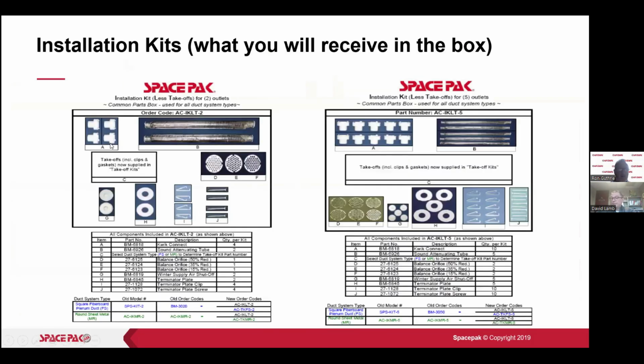Okay, these are the kits. They come with sound attenuators and connectors for the tubing. You've got your outlets, winter shutoffs for cooling-only systems, clips, screws, and the balancing orifices. You might want to use one of those in the typical dining room or downstairs bathroom that's really a closet. But you really don't want to use these anywhere else. You're best off just seeing how you do as far as the number of outlets you put into a room.